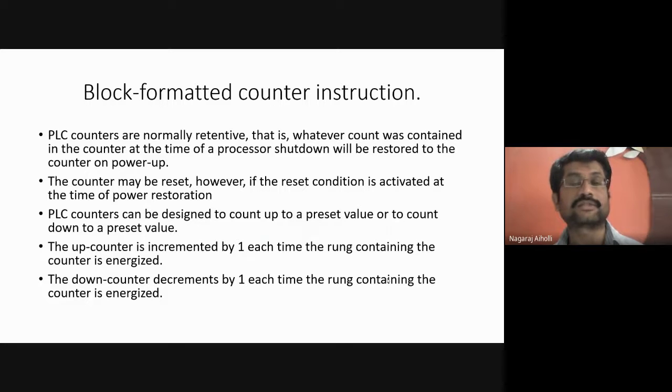This is one more difference between the timer and the counter. In the case of a timer, if there is a power supply off, the timer value becomes 0. But in the case of counters, even after a shutdown, that is power supply off, it does not become 0. Even after the power is restored, it will retain its original value. The counter may reset, however, if the reset condition is activated at the time of power restoration.